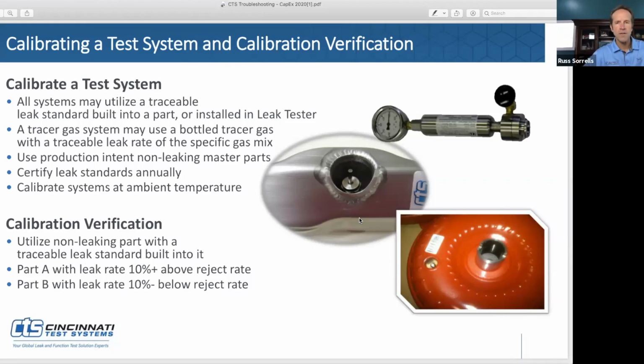What a lot of our customers do, just so, I know it seems complex here. If you look at the bottom, it says utilize no leaking part, then part A, part B. What you can have is one part, and you can cap off a quick connect on that part. That can be your no leak, and then you can put in the leak standard for the upper limit, verify that it rejects, and then you can put the leak standard in for the lower limit, make sure that it accepts. So you can use the same part, just have a quick connect that allows you to clip these leak standards in and out. Yep, absolutely.